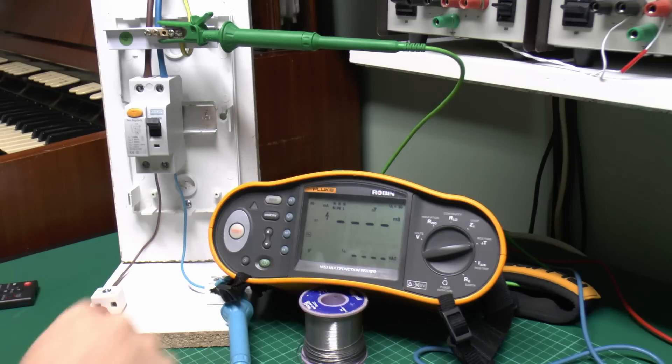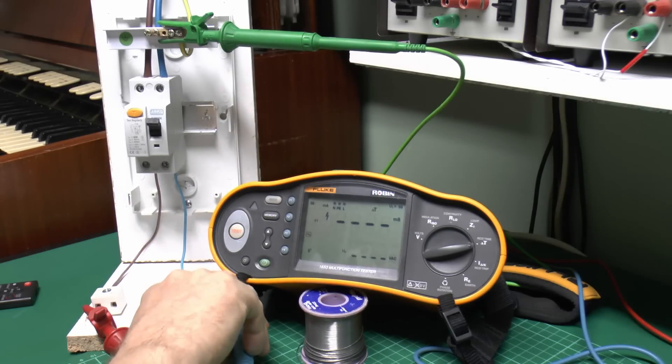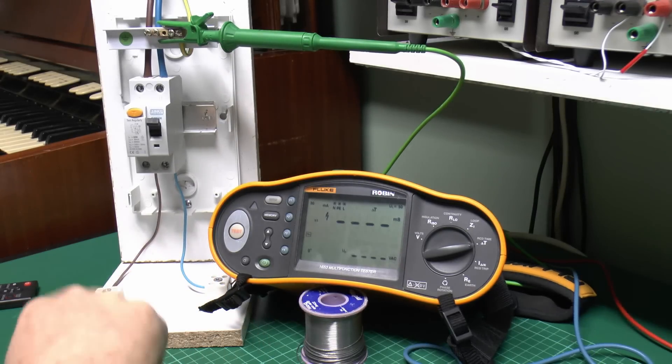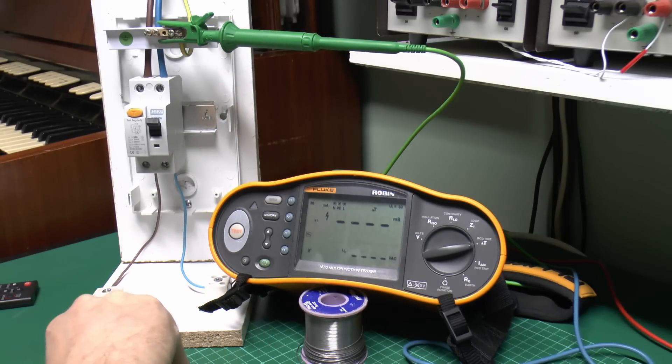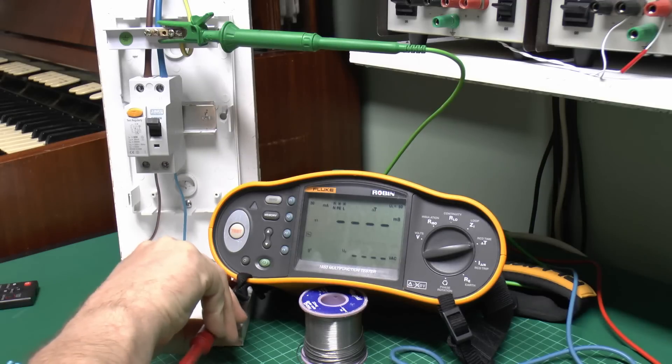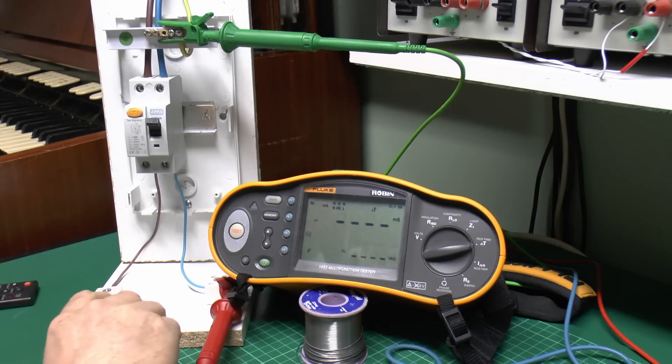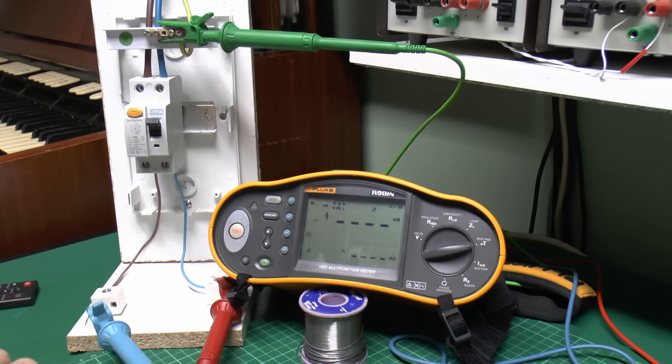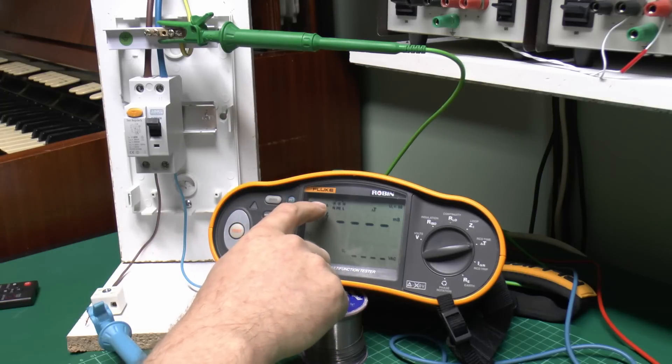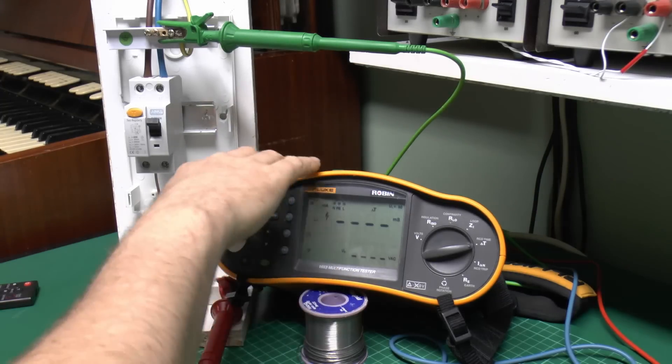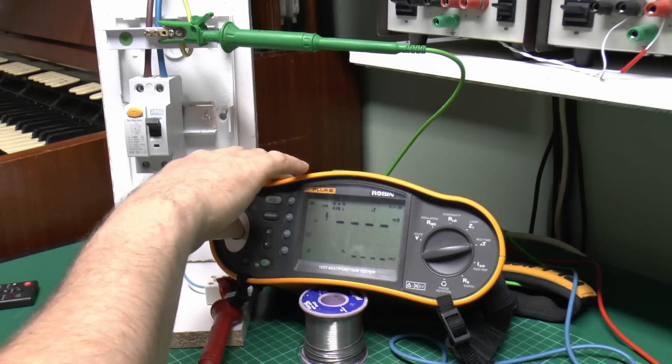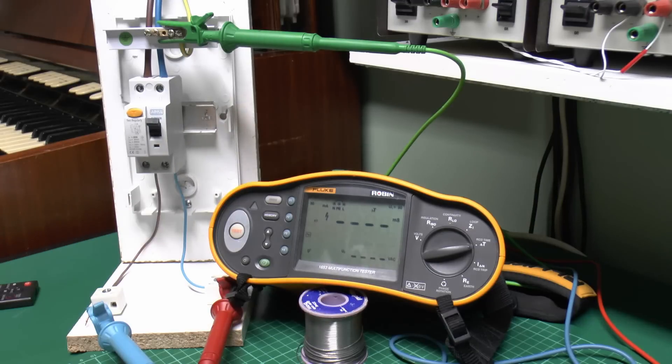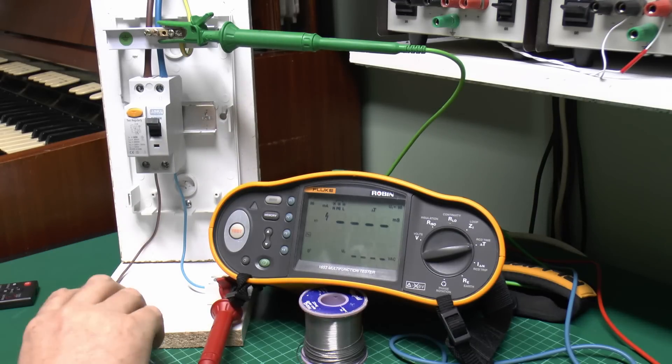And the other thing this does check for is reverse polarity, so if we were to swap these leads around, and for some stupid reason connect the red lead to the blue there, and the blue over here to the line, then it won't actually work. It actually shows here on the display that the neutral and line are reversed, and if you attempted to do the test, well it isn't going to work, so again that's just another thing it checks before actually doing the test.